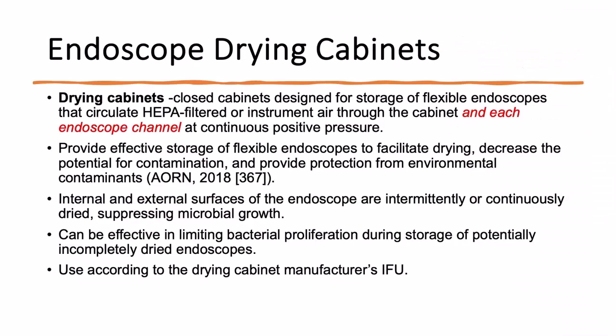Drying cabinets are closed cabinets designed for storage of flexible endoscopes that circulate HEPA-filtered or instrument air through the cabinet and each endoscope channel at continuous positive pressure. They provide very effective storage of your scopes to facilitate drying, decrease the potential for contamination, and provide protection from environmental contaminants. Internal and external surfaces of the endoscope are intermittently or continuously dried, suppressing microbial growth. They can be effective to limit bacterial growth during storage of potentially incompletely dried endoscopes, and you must follow the endoscope and the drying cabinet manufacturer's instructions.